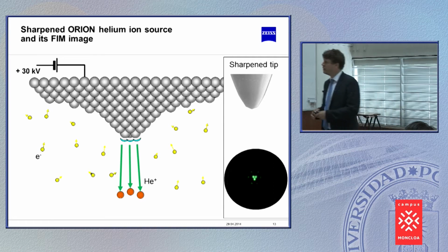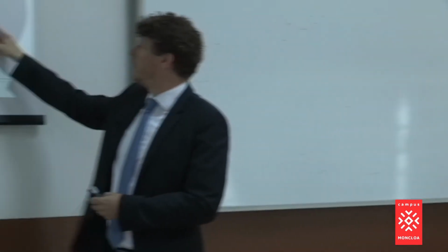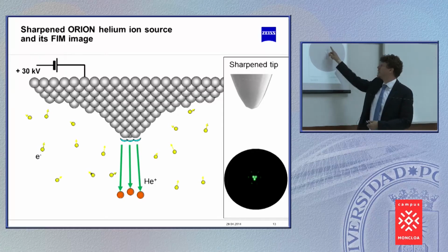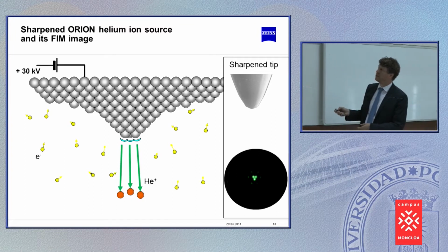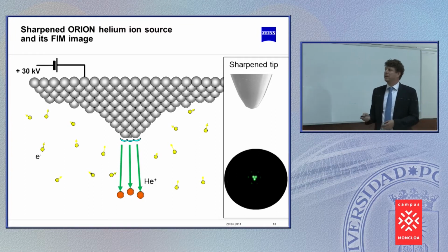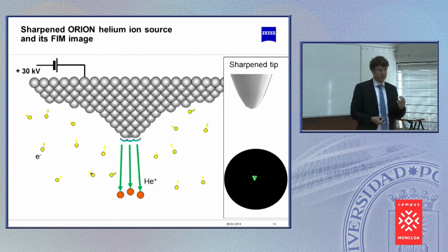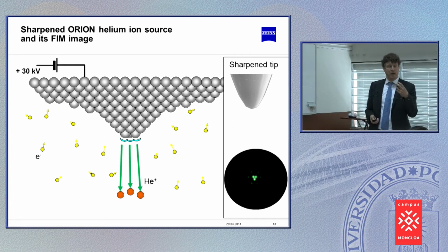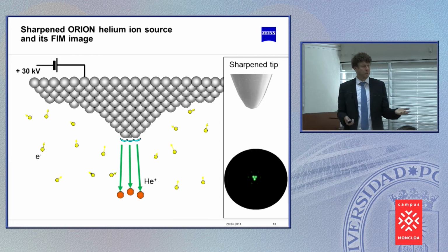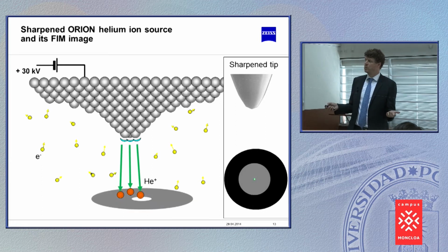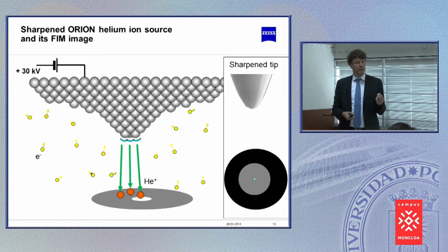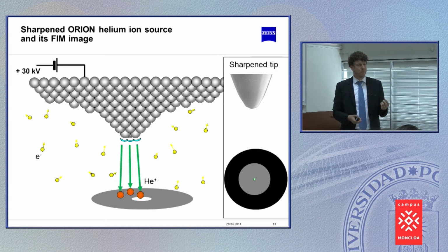And you see this here in the image. You don't see this very low intensity. The next neighbor atoms, you see this here, but what's important is these bright 3 spots inside, and really this cause our source. And then we use an aperture and use one single of this. So in this case we have really an atomic sharp probe size.